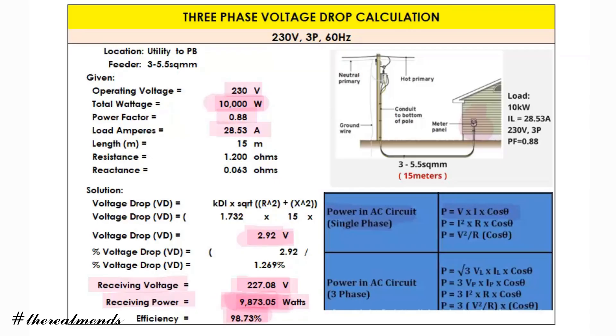The causes of voltage drop to consider: first is the length — the longer the length, the higher the voltage drop. Second is the conductor used — in this design we used copper, but what if you use aluminum? Third is the installation method. So before you design an electrical system, be sure to consider the voltage drop calculation, as this is how you know if the conductor is overloaded, undersized, or oversized.